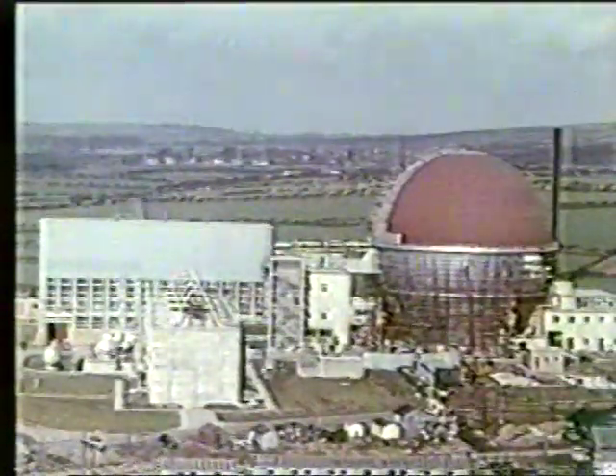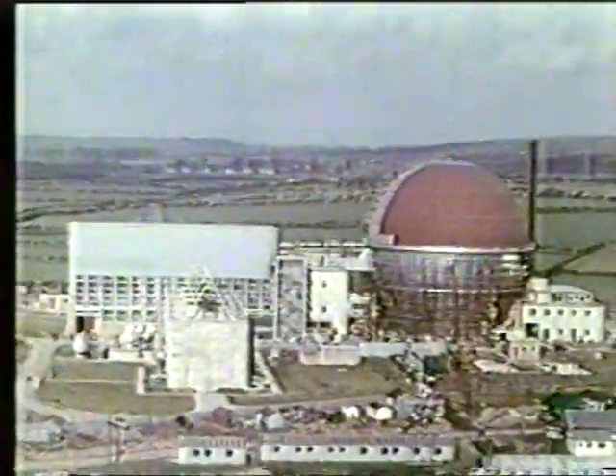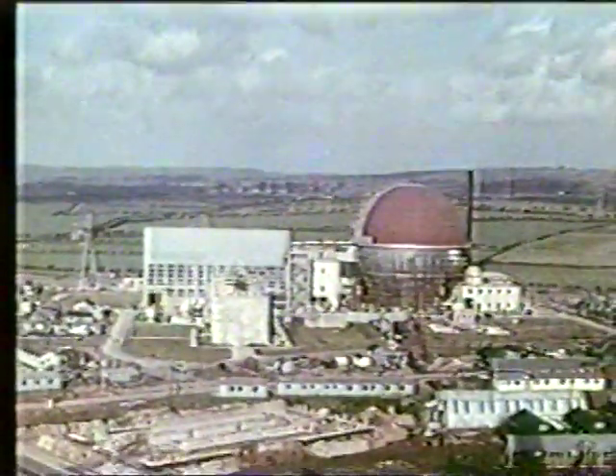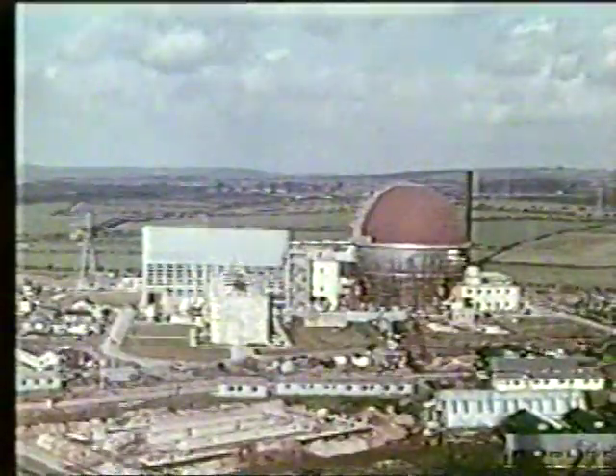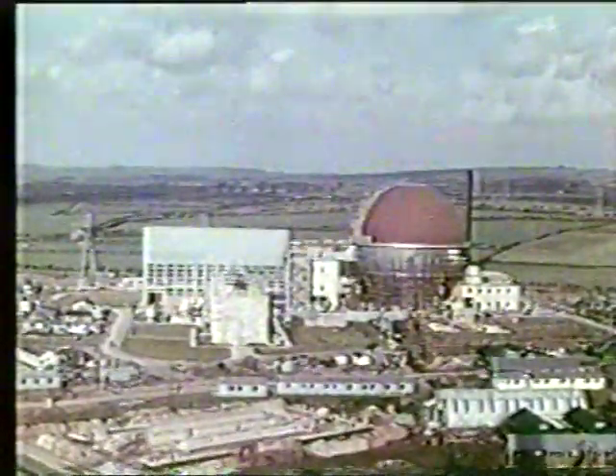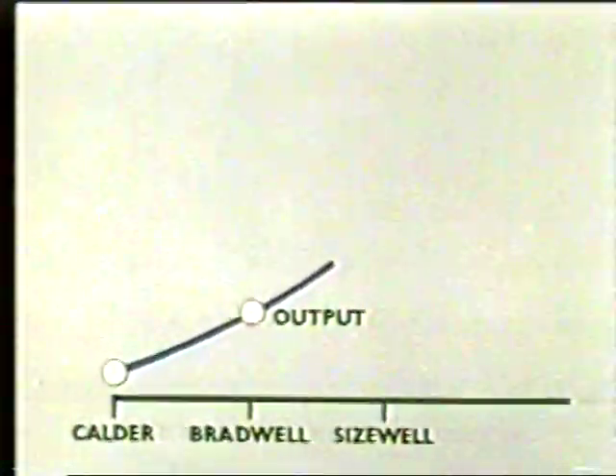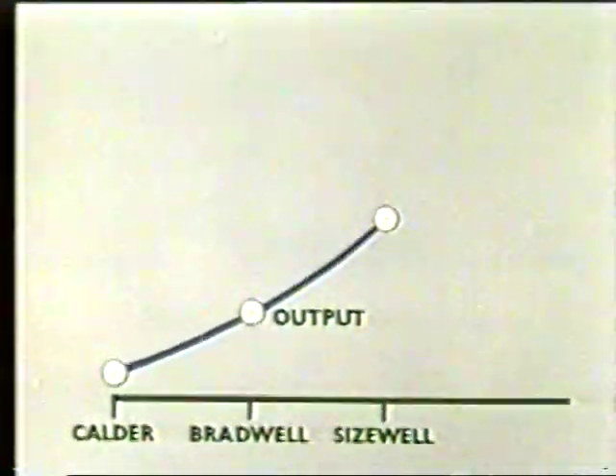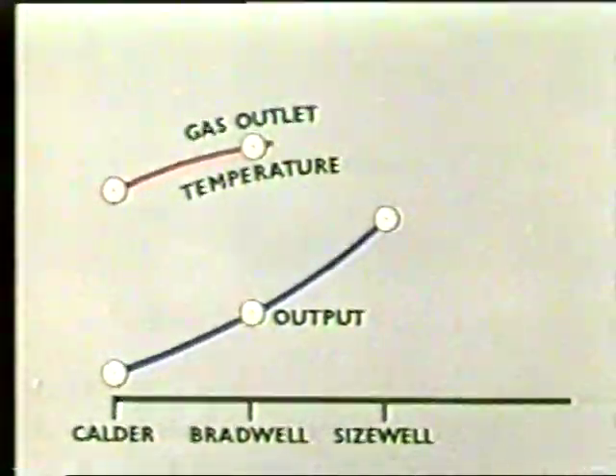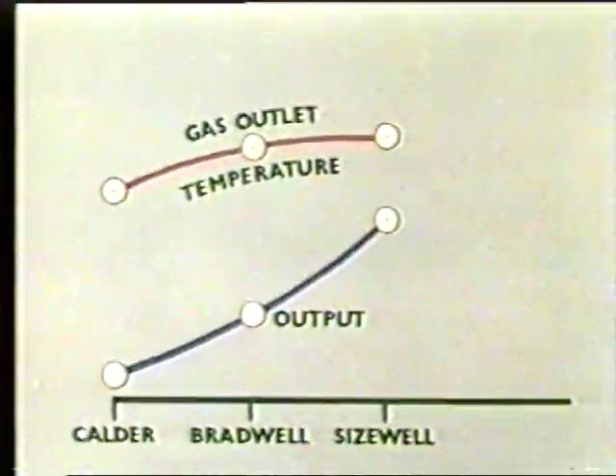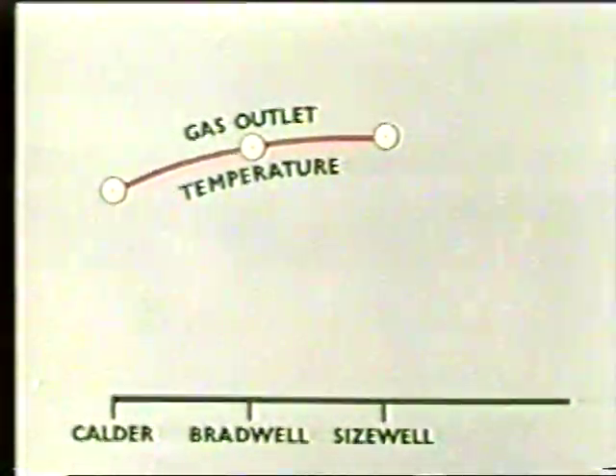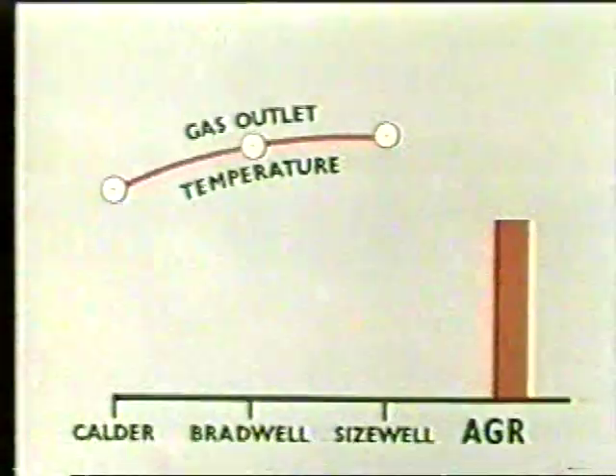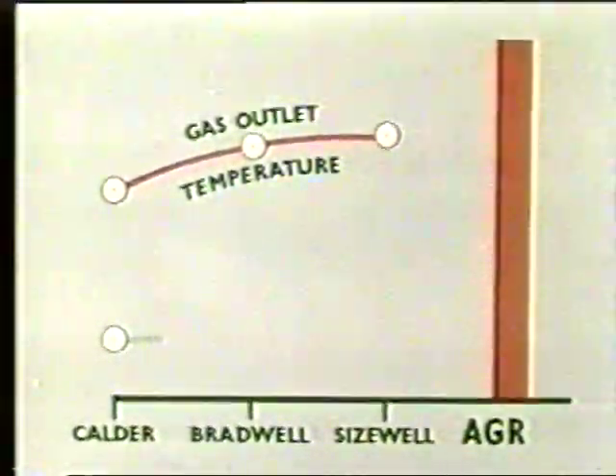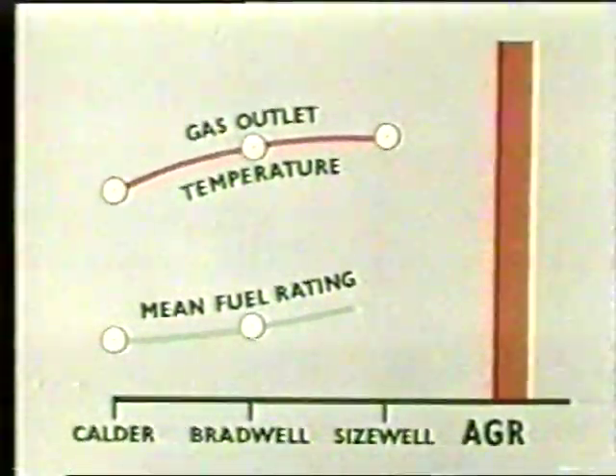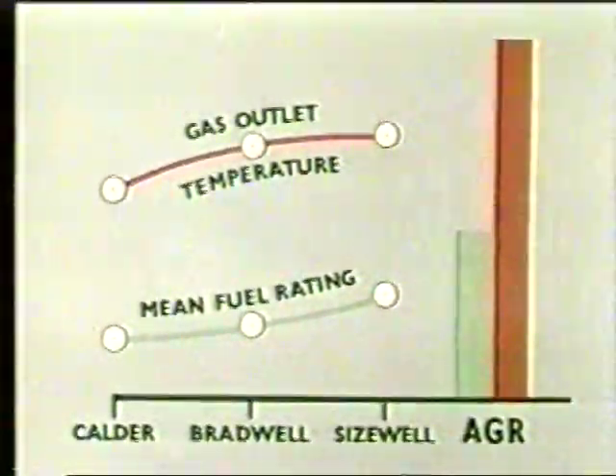The design of the advanced gas-cooled reactor is intended to ease siting problems, and its startup in 1962 will mark a notable advance in the graphite-moderated gas-cooled system. Although for the Magnox stations, output per reactor has risen from 36 megawatts at Calder to 290 at Sizewell, gas outlet temperatures are limited and have shown little improvement. In this respect, the AGR will be a big step forward. Again, the mean fuel rating at Sizewell is less than double that of Calder, but AGR will show a further threefold increase.